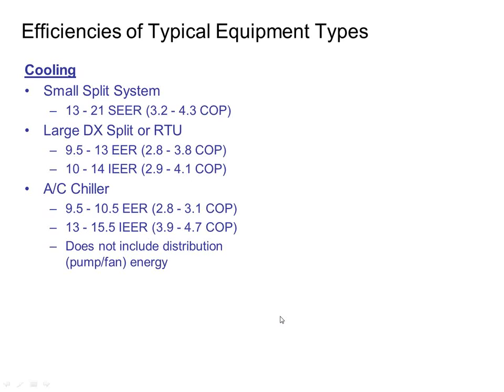When I get to larger stuff that's above 5 tons of capacity, we rate it in EER, energy efficiency ratio. It's a little bit different discussion than SEER. SEER takes into account cycling and counts and all that. EER is just straight efficiency on design day if it were ever to happen, right? And we rated equipment that way for a very long time. More recently, in the past 5-6 years, there's been this massive movement on these systems to start using IEER, which is Integrated Energy Efficiency Ratio.